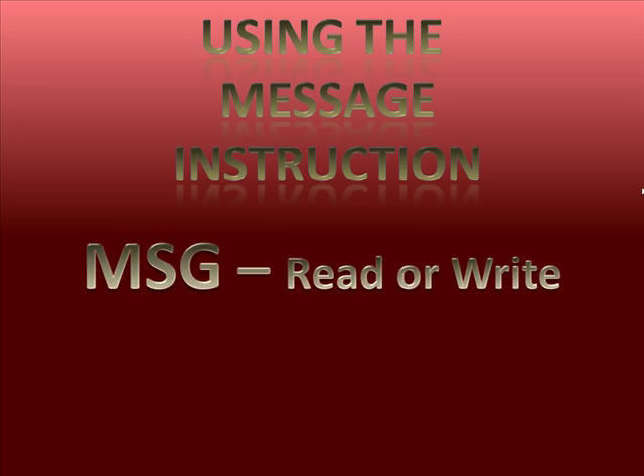Using the message instruction. Message read or write. There really is only one message instruction, and it can be set up as a read or a write. The message instructions, read and write, are used to directly read from or write to another PLC's data table without its consent or knowledge. Although these instructions use the communication ports on the controllers, they do not facilitate communications in the conventional sense. But it is a method for sharing data between processors and data tables.